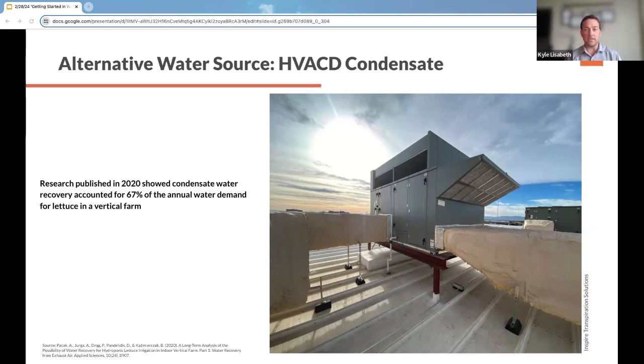Why is that condensate growing contaminants? It is hyper pure water. It's distilled water that's been condensed back into water. And it is picking up things from its environment, like VOCs in the air, or heavy metals that it touches, or microbial spores. So it is clean, but it can become dirty if we don't collect it very efficiently, store it, and condition it prior to reuse.